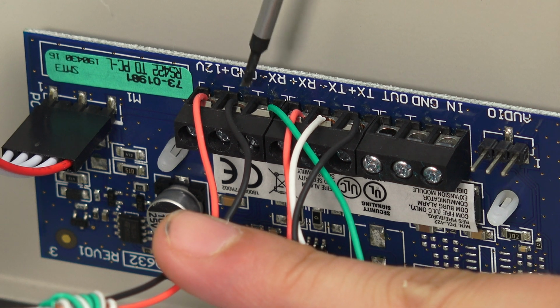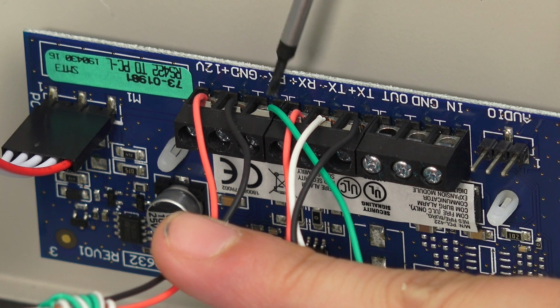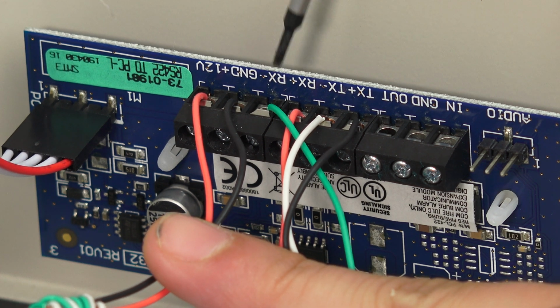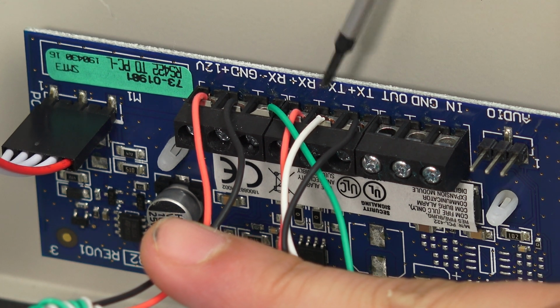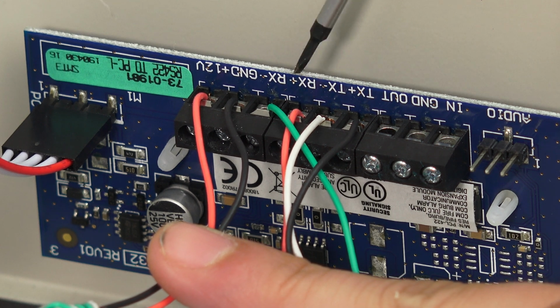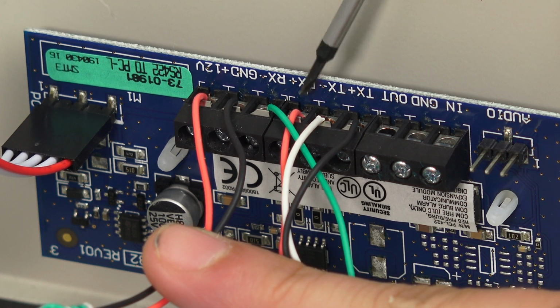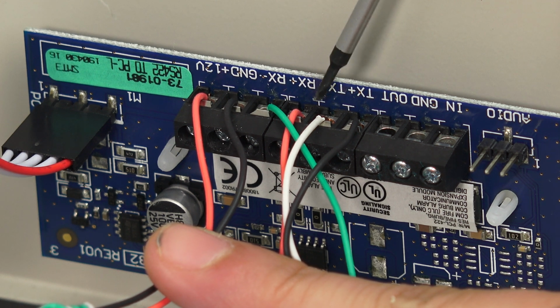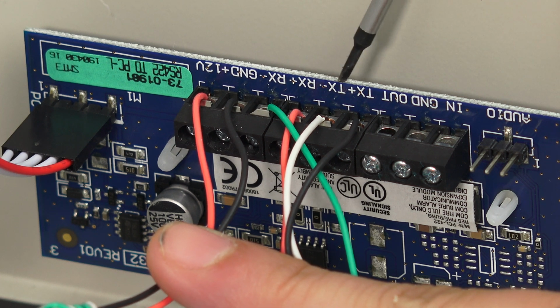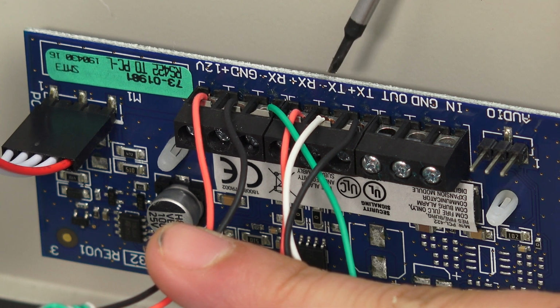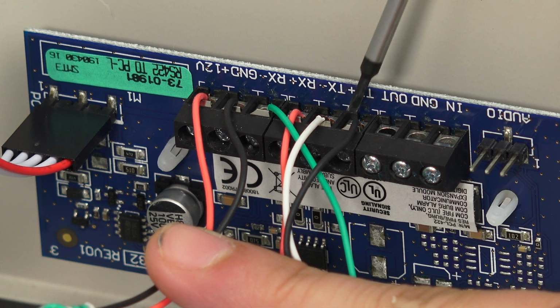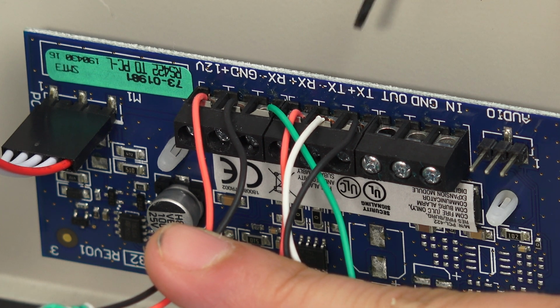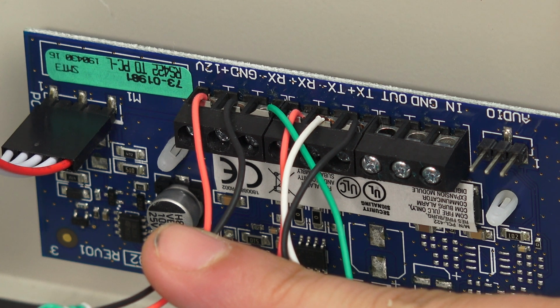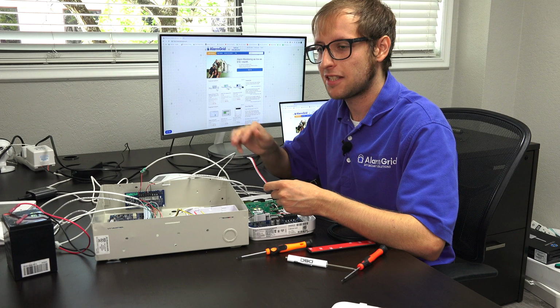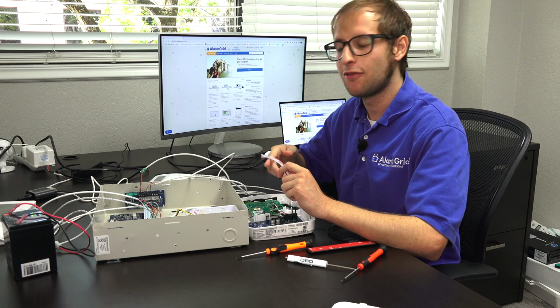First, we have the RX minus wire, which is going to the TX minus wire on the communicator, and that's the green wire here. And then we have the RX plus, which we're using a red wire in this case, and it's going to the TX plus connection on the communicator. And then we have TX minus. In this case, we used the white wire. So TX minus is going to RX minus on the communicator. And lastly, we have the TX plus, which we use the black wire, and that's going to the RX plus on the communicator.